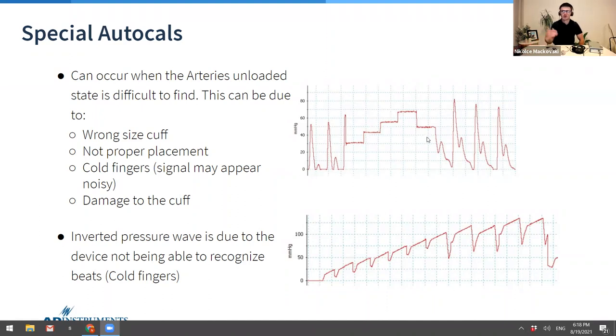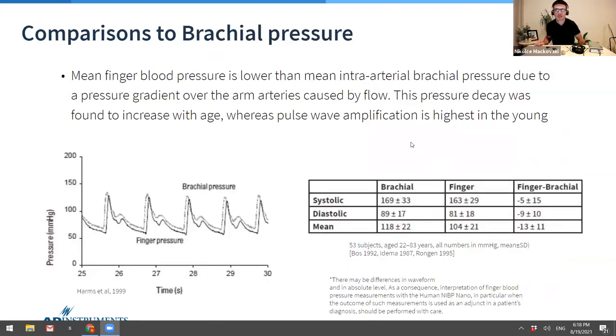Here you can actually see there are multiple steps. If you do see multiple steps, that means that the servo control center is just trying to find that proper set point within the arteries to keep them at an unloaded state. So how does it compare to, let's just say, the brachial pressure? Generally the finger pressure will be lower than the mean intra-arterial brachial pressure due to a pressure gradient over the arms caused by flow. This has been well published in various publications. Typically we see around 10 millimeters of mercury less in the finger pressure relative to brachial pressure. This study here by Harms et al. 1999 looks into how we do have a little bit of a time lag between the brachial versus the finger. But for this gentleman, who was in his 20s, the actual waveform itself almost looks identical.